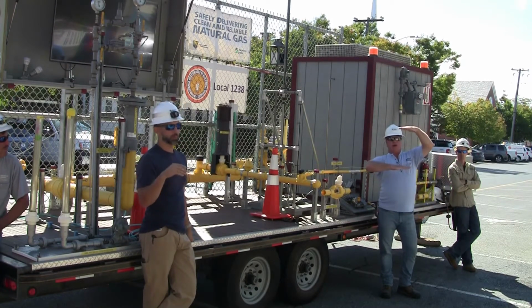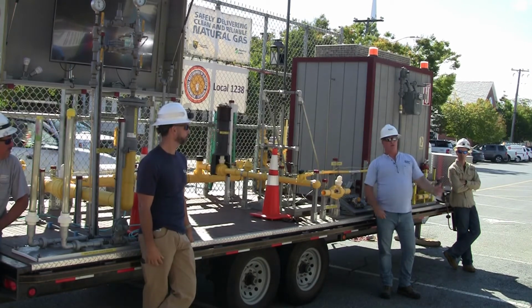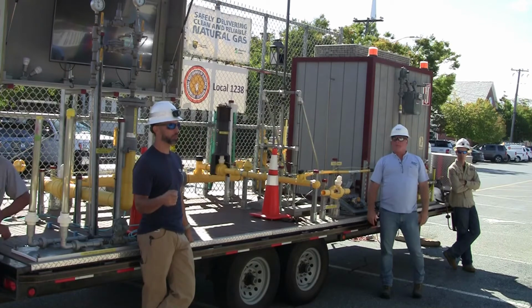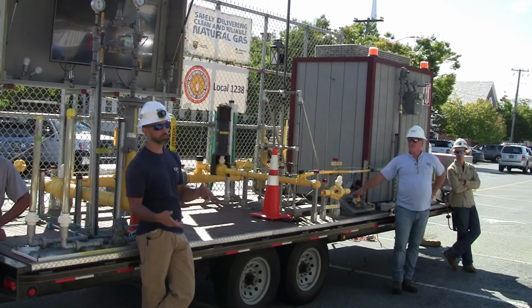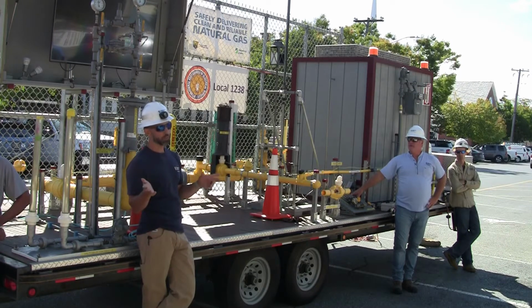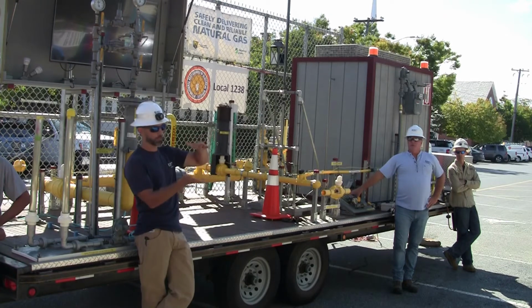It's a steel piece on top and bottom. We can squeeze from half-inch all the way up to 8. We have both hydraulic ones and manual ones. Half-inch to 6-inch we can do by hand. You can do the 6 and 8 by hand, but it's not fun. So we have hydraulic ones that you really just pump, and as you pump, they just squeeze it down.